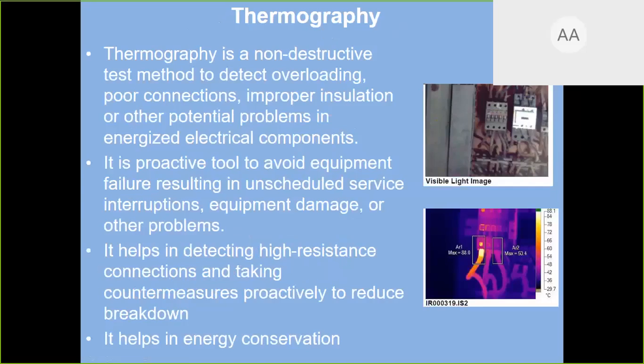And another is thermography. You must have heard that Maruti is now insisting all their vendors have thermography. Why is thermography required? Thermography is a non-destructive test method to detect overloading, poor connection, improper insulation, or other potential problems in energized electrical components.